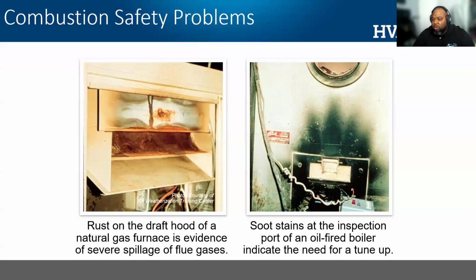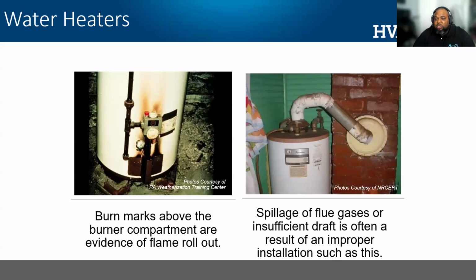If you see evidence of rust on equipment or you see soot, these are key indications that you've got a combustion safety problem and that you may have the likelihood of carbon monoxide entering the building. As inspectors or auditors, or just from a homeowner's perspective, no matter where you are, if you see stuff like this and you don't have the expertise, definitely tag in a professional to assist. Other issues, looking at the left image here, this water heater, they don't come with the flame marks here. That indicates a problem. So, with that being said, testing will help to identify if you have a carbon monoxide issue.